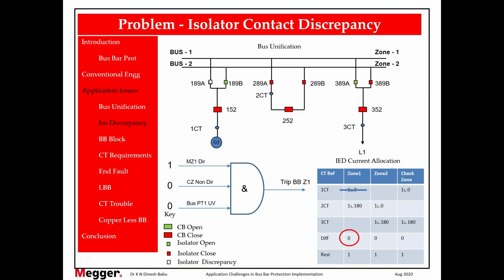So in the absence of fault, because of this check zone, and in addition to this, your bus PT under voltage is there, it will provide security. Now you may have a question, check zone is already there, then why do you need bus PT? There can be problems when check zone also would fail, because we will discuss that during CT trouble. Because when CT itself is having a problem, main zone and check zone both will have a problem. That time the bus PT under voltage will come into picture.